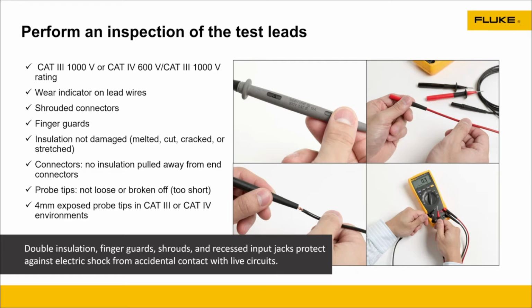But again, part of this is inspecting them, making sure that your test leads are not wearing down. They're not fraying, like in that bottom left picture where you can actually see exposed metal. If you were touching 480 volts and you happened to touch that, you would get shocked. There's a safety problem there. Some test leads actually are double layered. As they start wearing out, you'll start seeing another color underneath that initial layer. It's time to replace them.